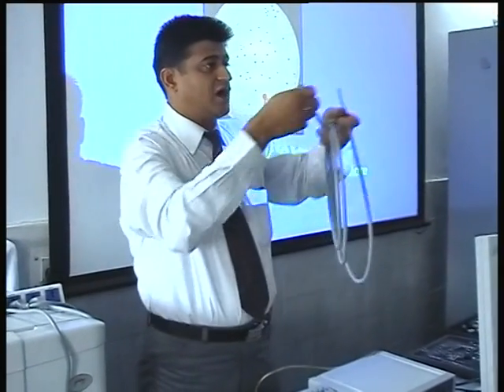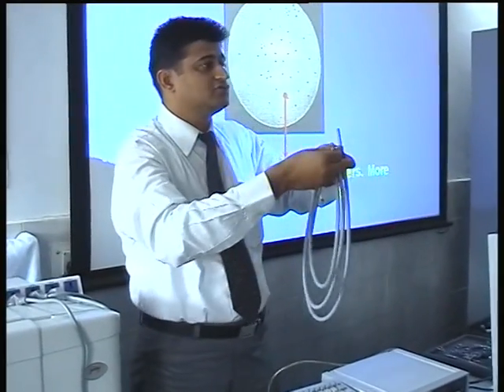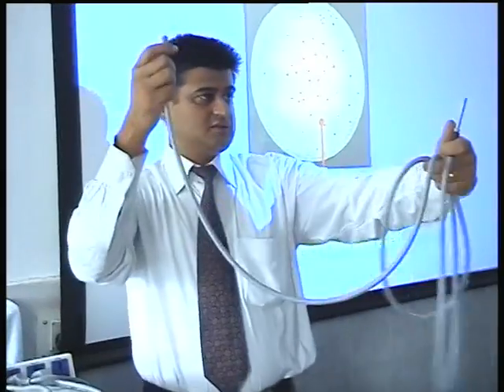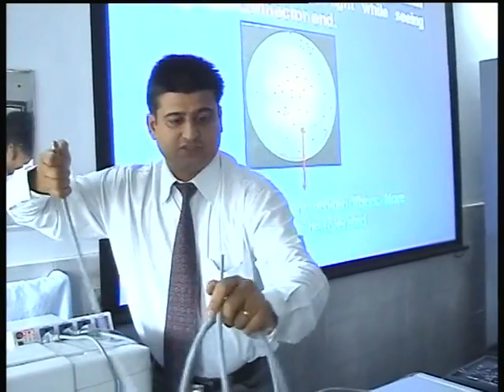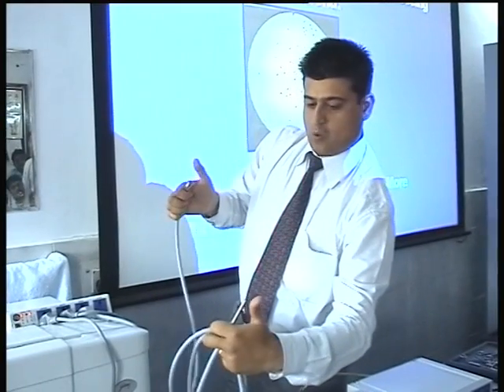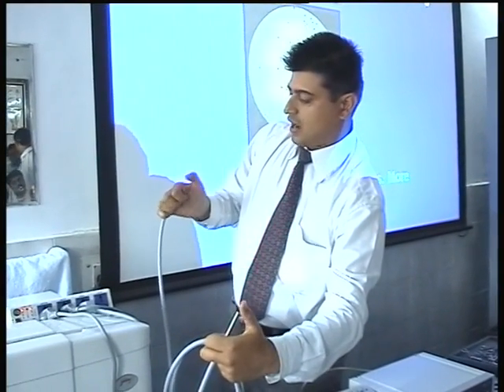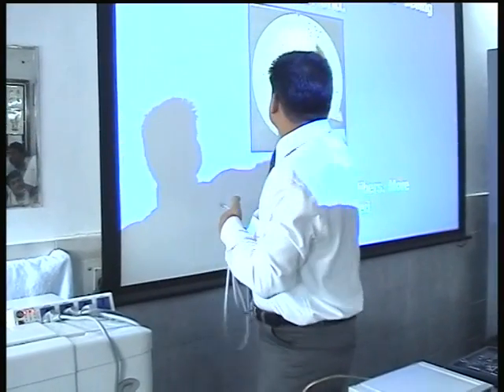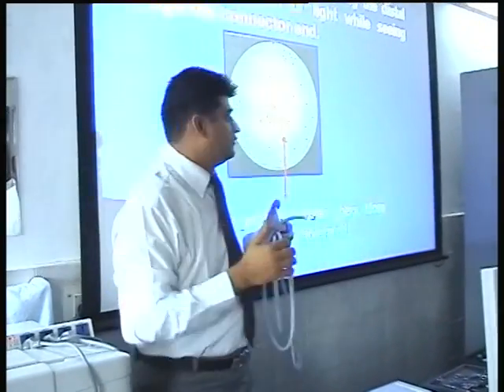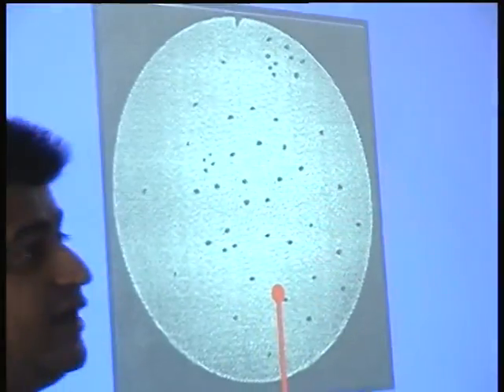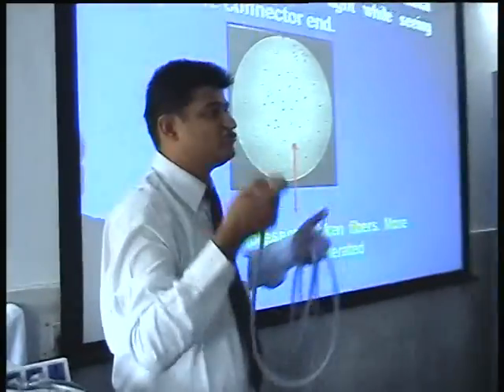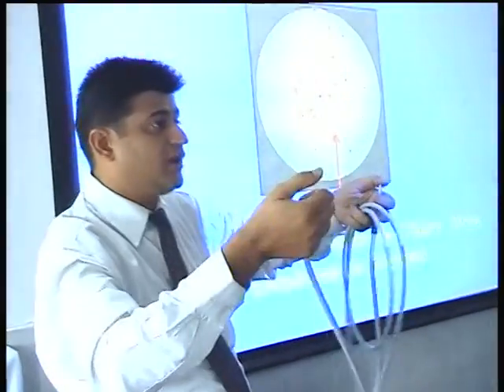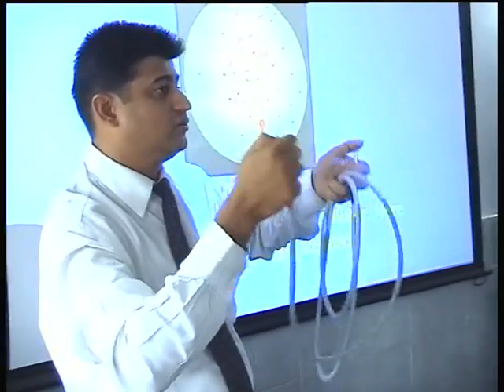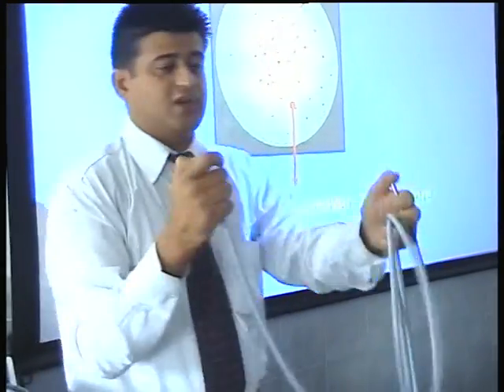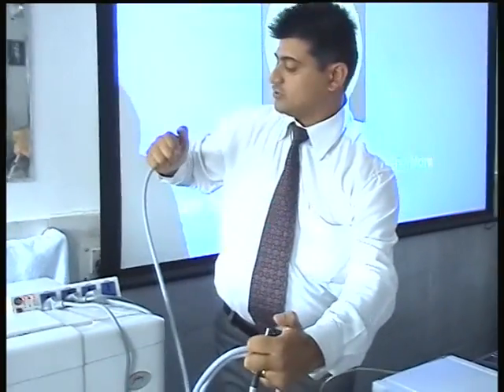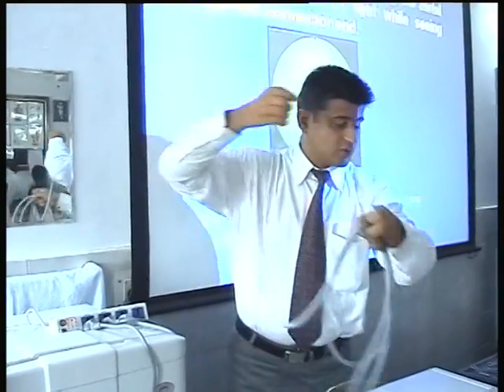So how to check whether after a couple of months or years my light cable is really up to the mark or not? How we do it, you take this fiber optic cable in the daylight, you stand there, and then you push over here, you come here and try to see this area after you clean it thoroughly, and you will find some black spots over here. If the black spots cover an area beyond 25%, you should change your light cable, because especially in the neuroendoscopic procedure you definitely need a very high intensity, good illumination inside. So this is how we check. You can also physically check, and these are the steps how to see. When you go in the light, you can see that these broken fibers are there.